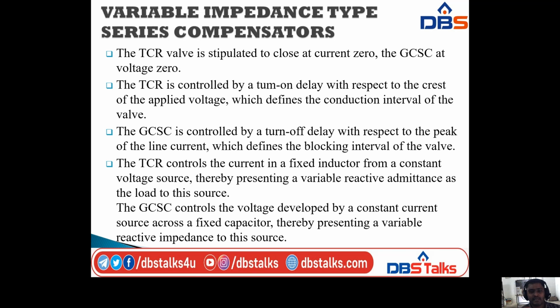So the TCR controls the current in a fixed inductor from a constant voltage source, thereby presenting a variable reactive admittance as a load to this source, and the GCSC controls the voltage developed by a constant current source across a fixed capacitor, thereby presenting a variable reactive impedance to this source. This is the difference between the TCR and GCSC schemes.